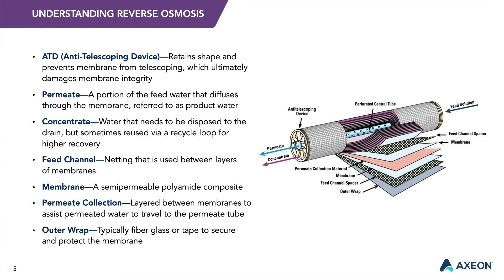In membrane systems, the elements are placed in series inside of a pressure vessel. The concentrate of the first element becomes the feed to the second element, and so on. The permeate tubes are connected with interconnectors, also called couplers, and the combined total permeate exits the pressure vessel at one side and sometimes at both sides of the vessel.